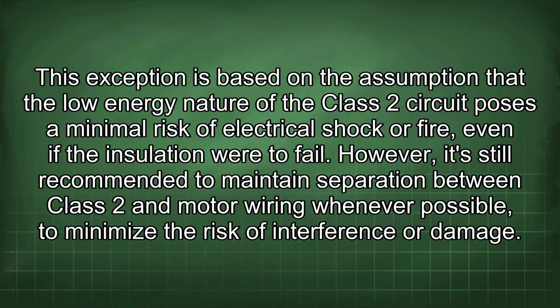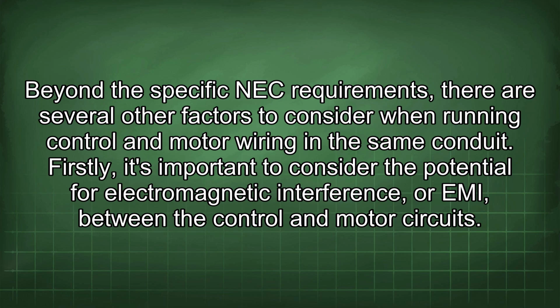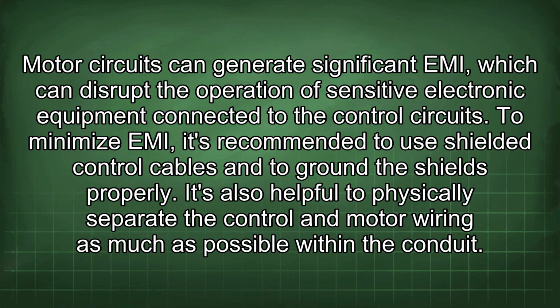Beyond the specific NEC requirements, there are several other factors to consider when running control and motor wiring in the same conduit. Firstly, it's important to consider the potential for electromagnetic interference, or EMI, between the control and motor circuits. Motor circuits can generate significant EMI, which can disrupt the operation of sensitive electronic equipment connected to the control circuits. To minimize EMI, it's recommended to use shielded control cables and to ground the shields properly. It's also helpful to physically separate the control and motor wiring as much as possible within the conduit.